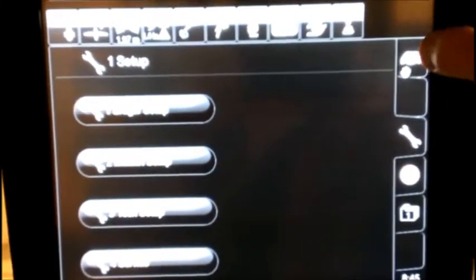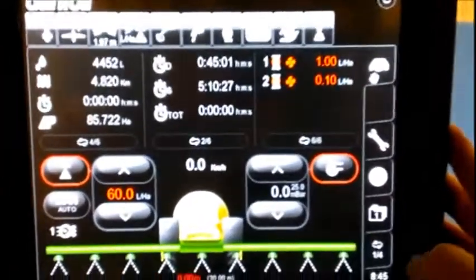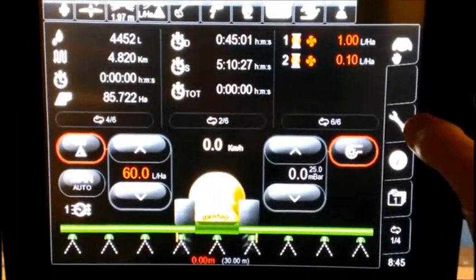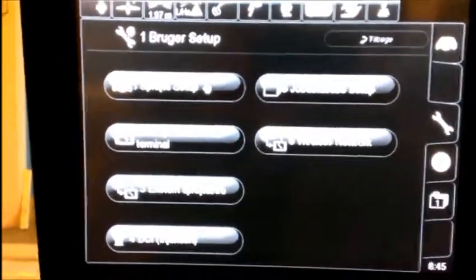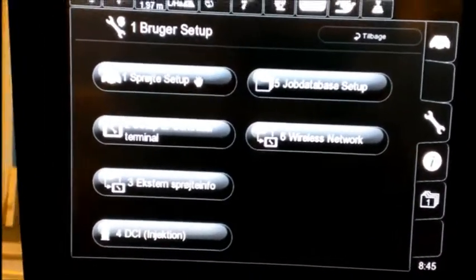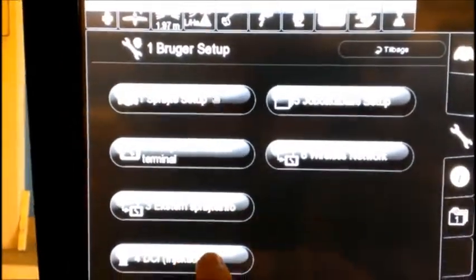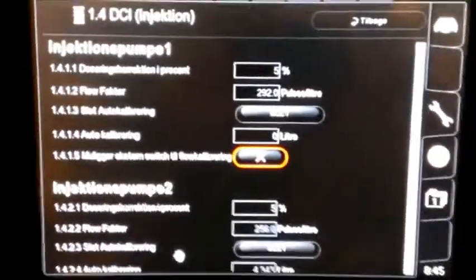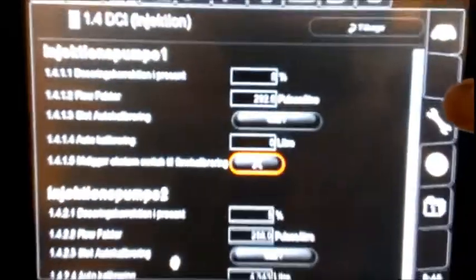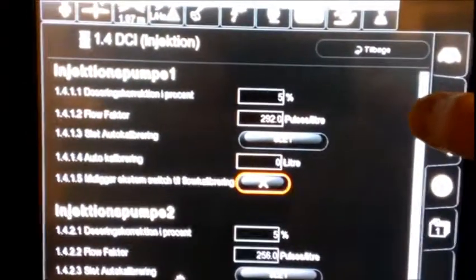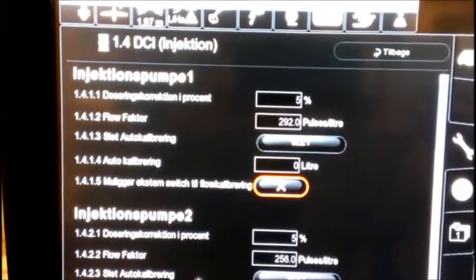In order to start the calibration, go into the PC monitor, and the first thing you do is press on the key, and then you press user setup, and then you have number 4, DC injection. You press this one.